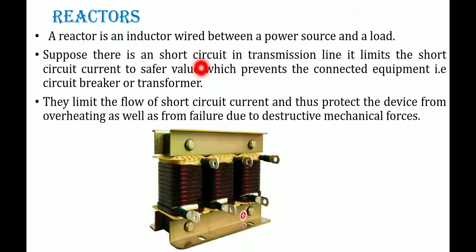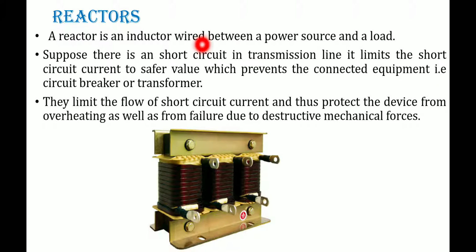In case a short circuit occurs, which is also a kind of fault, if it takes place in the transmission lines, the reactor limits that short circuit current to a safer value, thereby avoiding damage to connected equipment like the circuit breaker, transformer, and relays. So the connected equipment stays on the safer side.